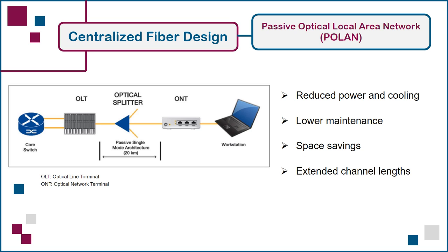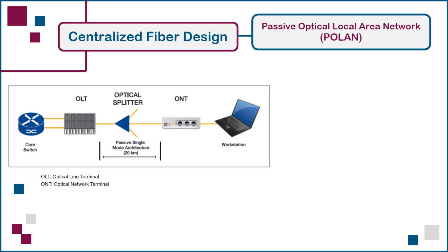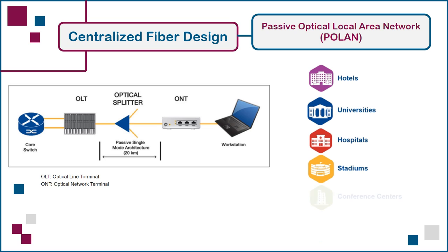The extended reach of single-mode fiber makes it possible to provide network services from a single distributor room to every device on a multi-building campus, over links that can be as long as 20 kilometers. This centralized grouping of network devices is inherently easier to physically secure than a collection of rooms on various floors, especially when dealing with high-rise buildings or multi-building campuses. POLAN architecture can be used to deliver network services in dedicated facilities, such as hotels, university campuses, hospitals, sports stadiums, and conference centers, in addition to commercial or office buildings. The common element is a large space with many network devices spread out over extended distances. These types of facilities are best suited to take advantage of single-mode fiber's reach and bandwidth capabilities.